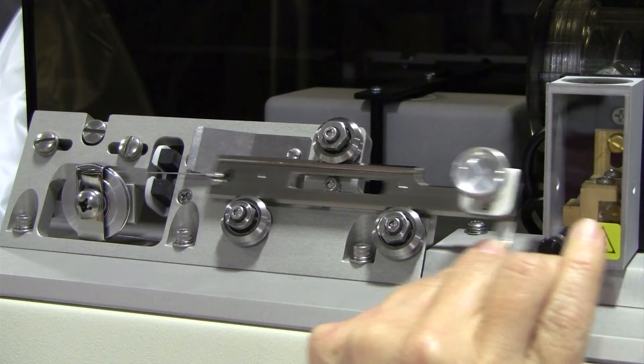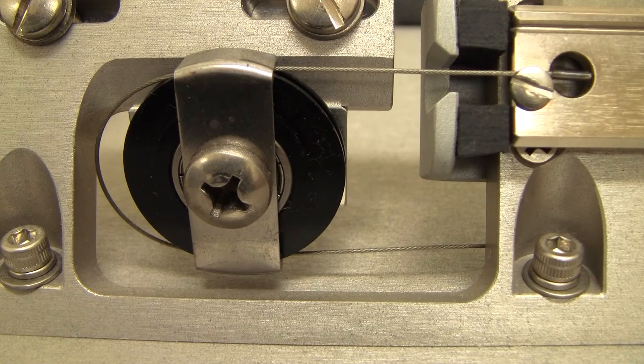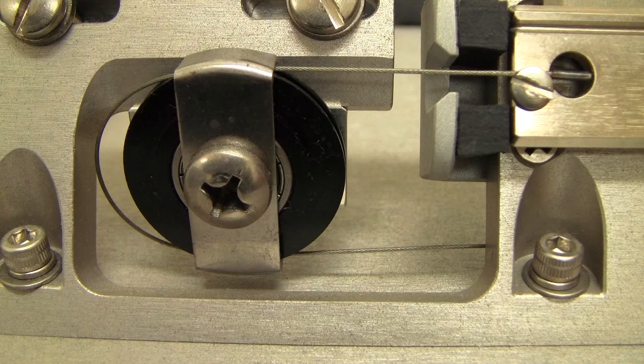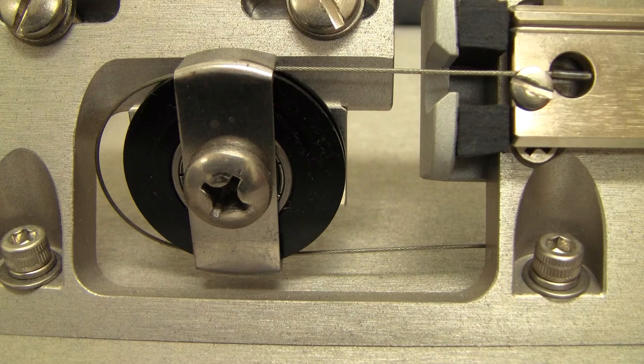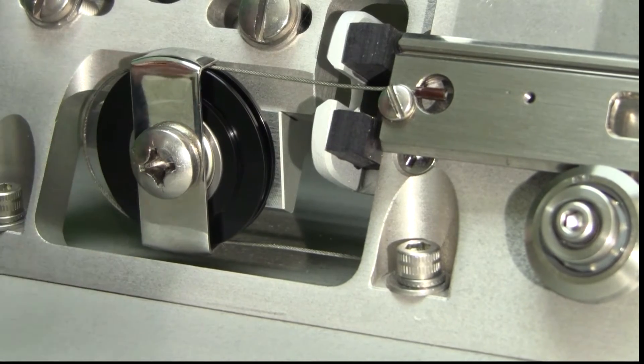To test the pulleys for proper operation make sure the puller bars are clipped into their spring stops. In this position there's about a quarter inch of slack between the pulley and the pull cable. Now spin the pulley like this. If it spins for a full revolution or more you are good.